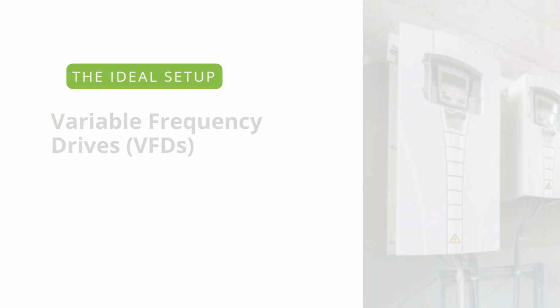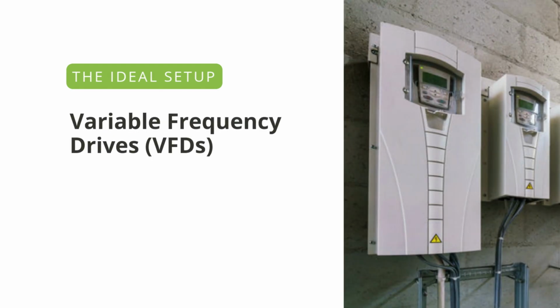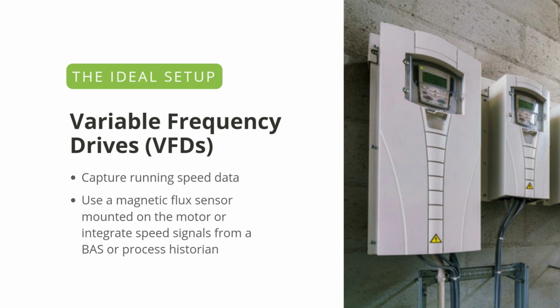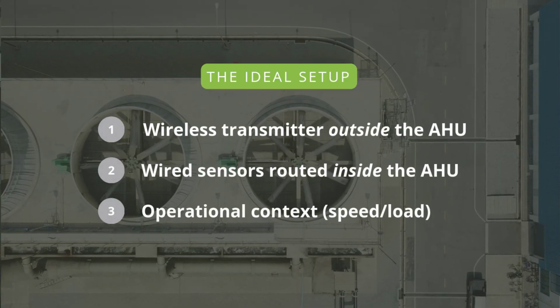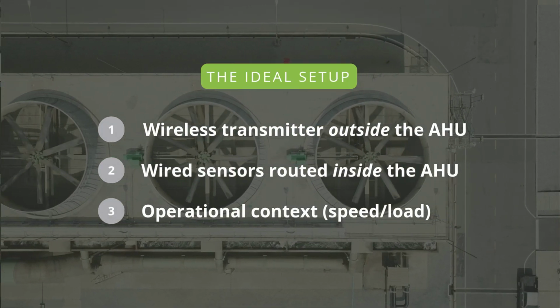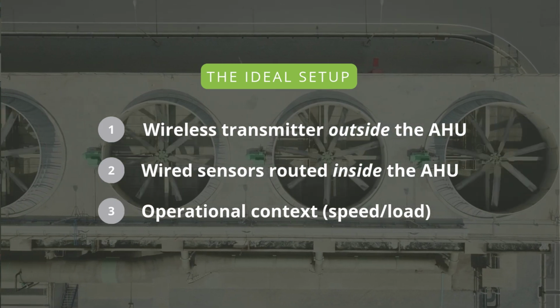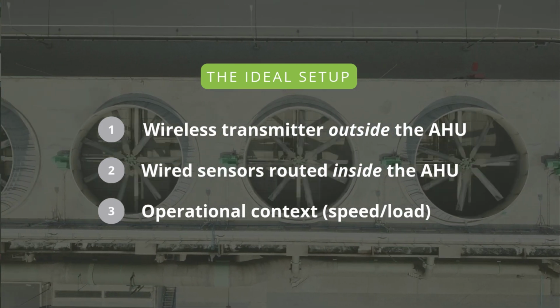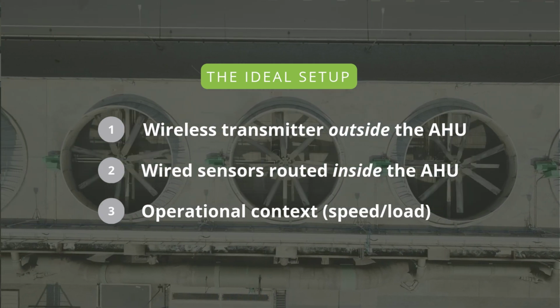If the AHU is driven by a variable frequency drive, or VFD, it's important to also capture running speed data. This can be done using a magnetic flux sensor mounted on the motor or by integrating speed signals from a building automation system or a process historian. This setup allows you to collect all the critical condition data and transmit it wirelessly for real-time analysis. It also provides the context needed to diagnose faults accurately and detect emerging issues as early as possible. Here are some real-world examples of how facilities have used this exact monitoring setup to identify and resolve AHU issues before they led to failure.